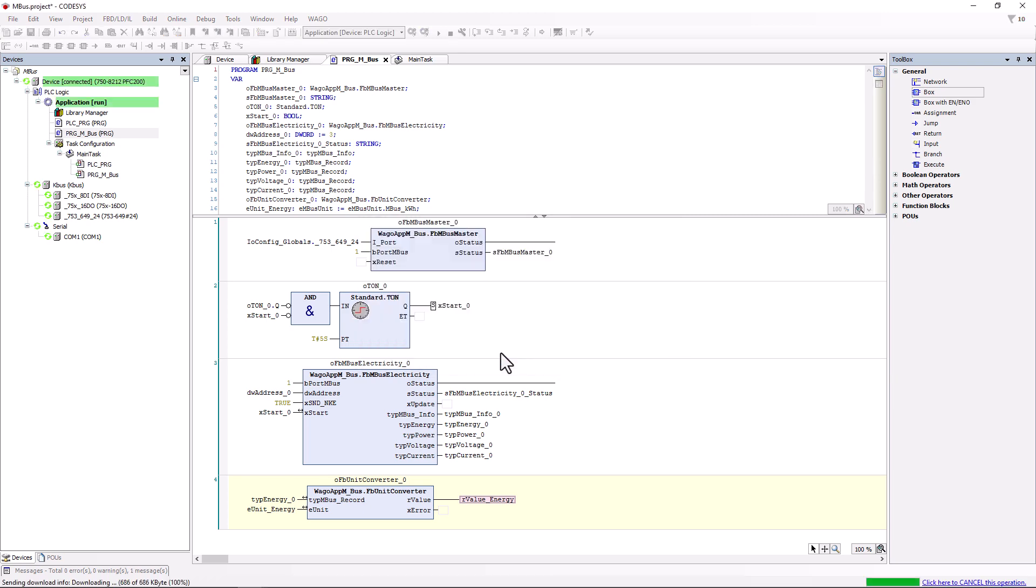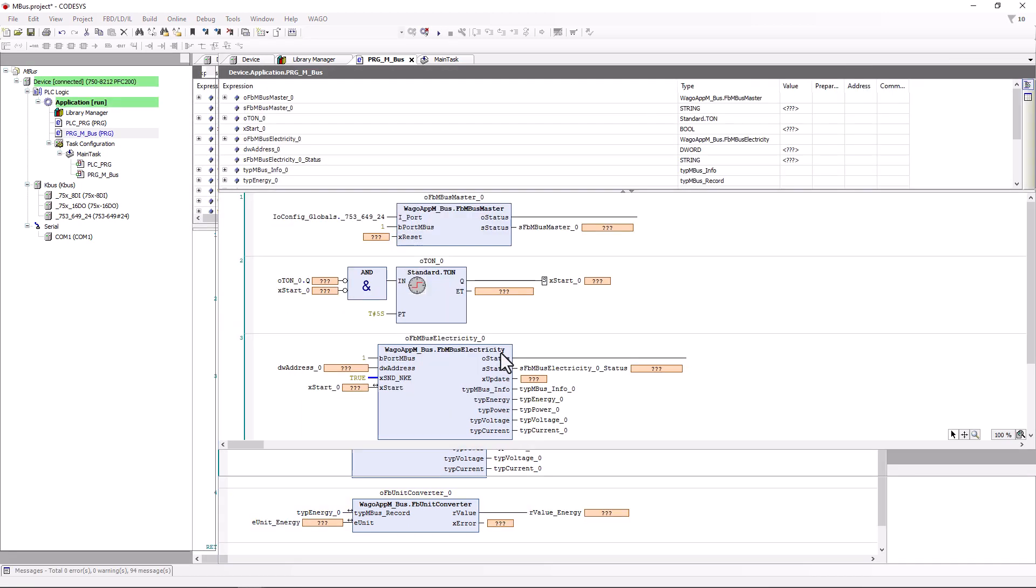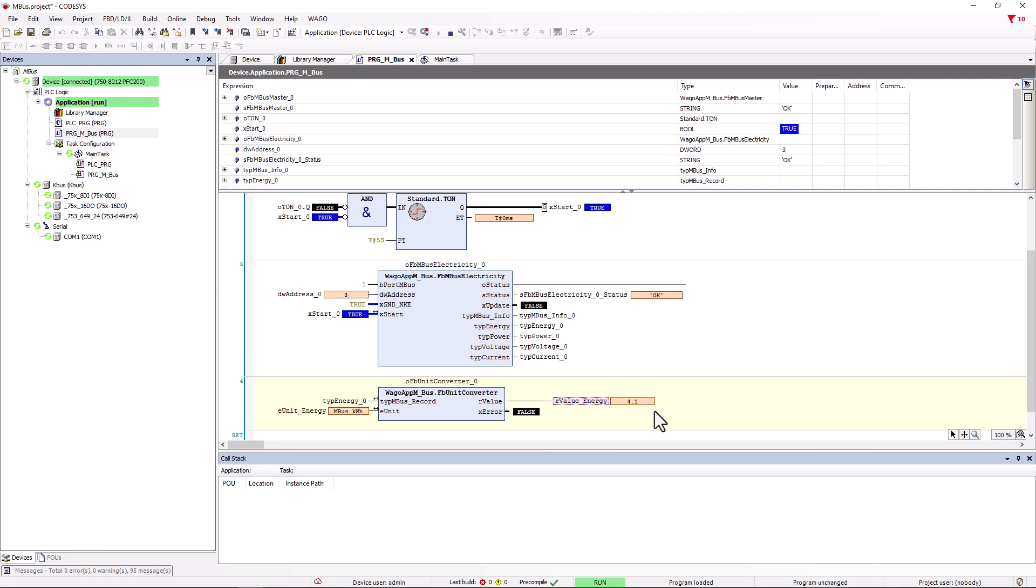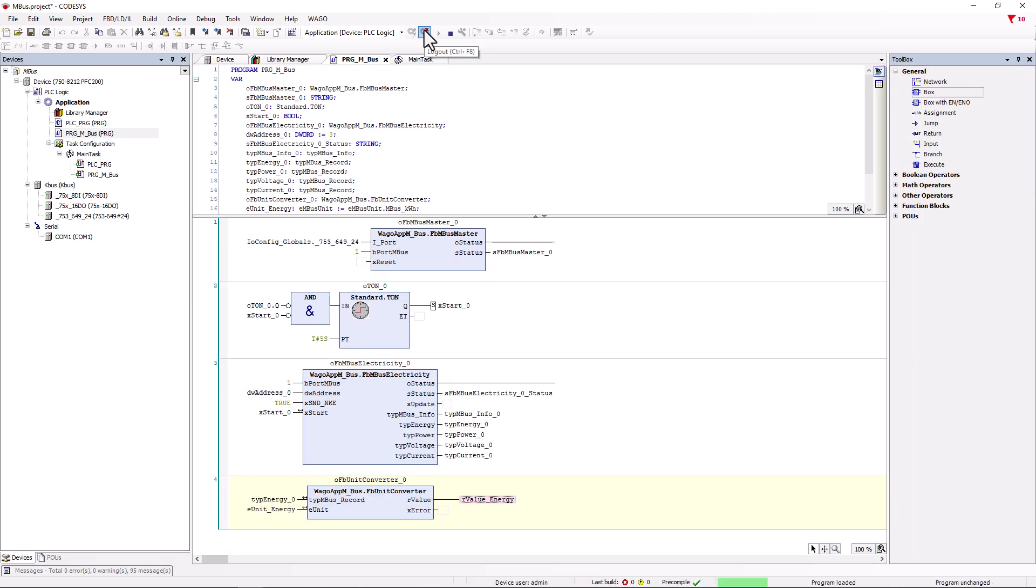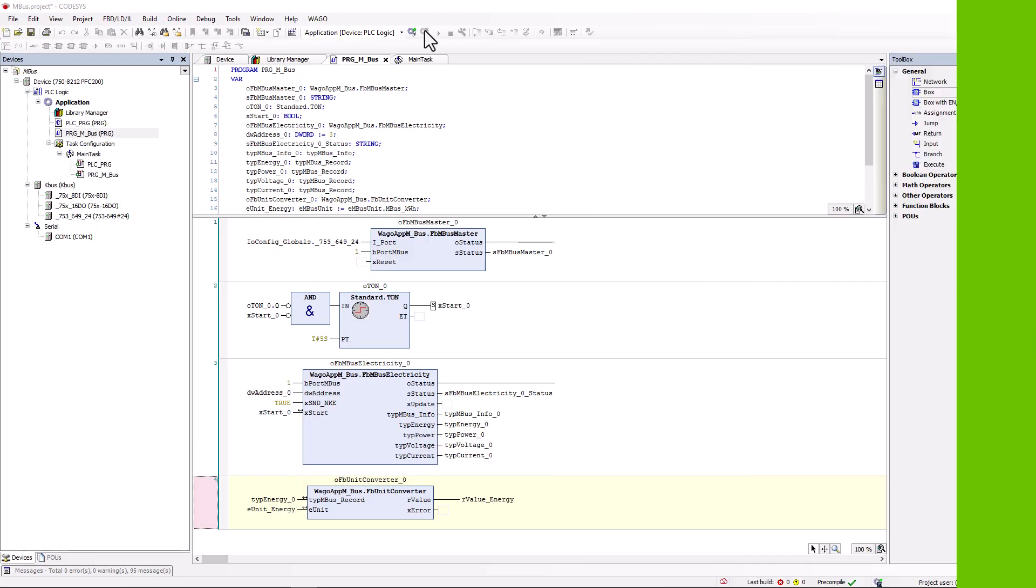We log in, start the controller and see the energy value in kWh in the R_value_energy variable. With the function block FB_MBUS_electricity, we can read out the total meter values for energy, power, voltage and current. In most cases, however, a meter provides significantly more data. These can be read with the function block FB_MBUS_Multitel.